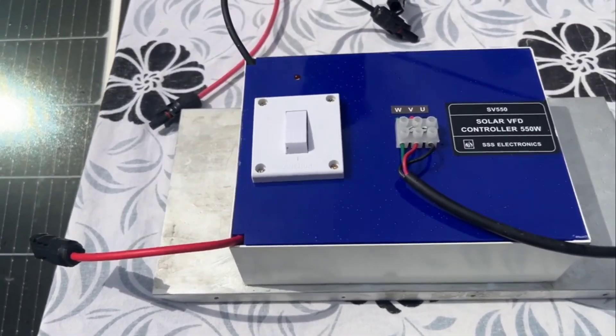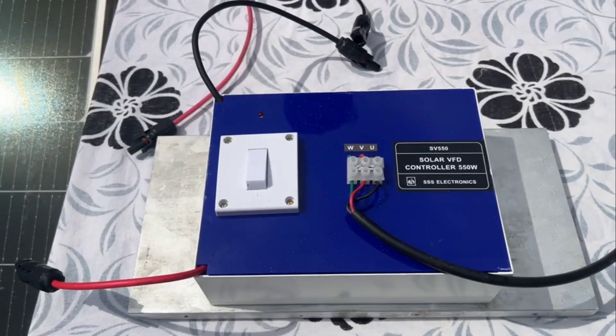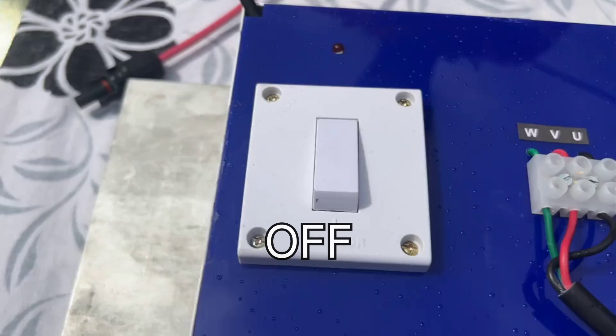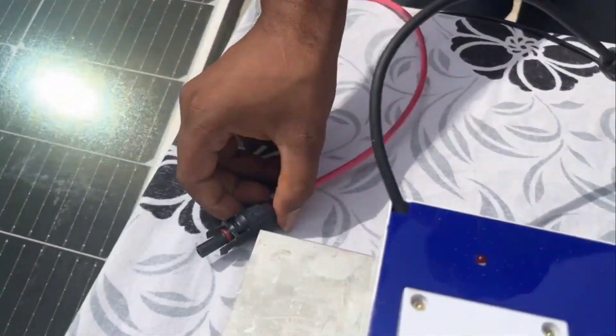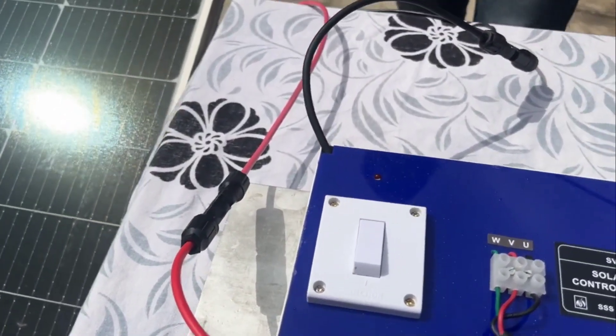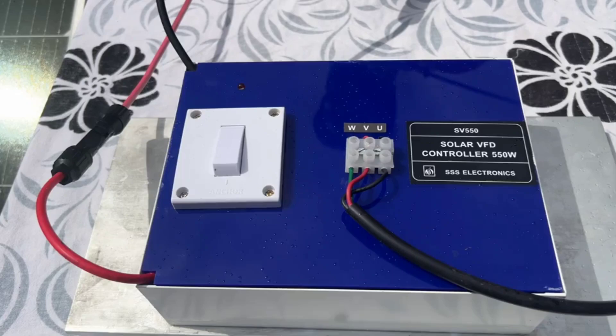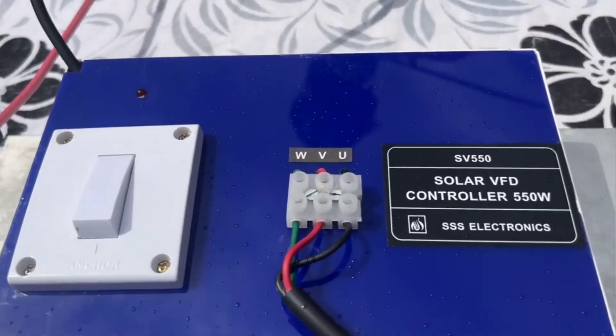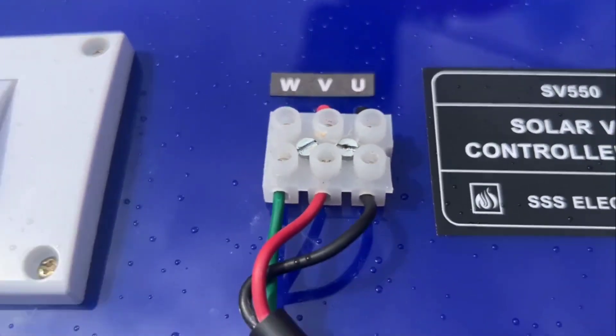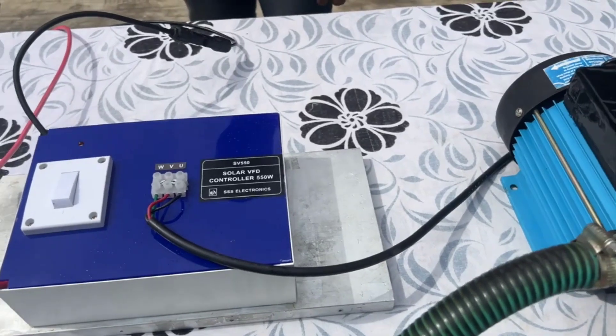Connecting the solar panel to the solar VFD is pretty straightforward. Keep the switch on the solar VFD in the off position and plug in the solar panel using MC4 connectors. You don't have to worry about the polarity — plus and minus — just connect them the way they match. The solar VFD has three output wires labeled U, V, and W. They have to be connected to the corresponding terminals of the water pump, also labeled as U, V, and W.